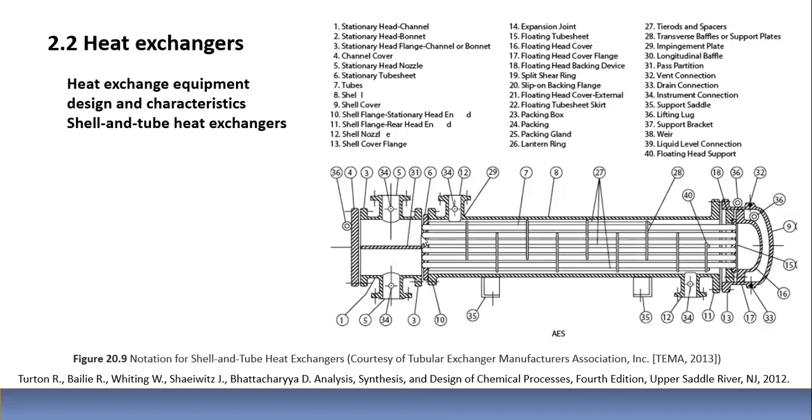En corte, se observa así. Usted ve los tubos soldados en el espejo. Mire que usted puede retirar este cabezal. Implica, según el dibujo, que eso está apernado. Pasa un perno, pasa una tuerca y seguramente en el círculo del cabezal, en el círculo de esta brida, esto es una brida, se ve el corte aquí, acá hay otra brida. A lo largo de ese círculo de la brida, usted puede ver esta línea aquí, por donde va a pasar el perno. Se aprieta con una tuerca y se hace un torqueo en cruz hasta que se aprieta todo. Del lado del cabezal, lo mismo se hace del lado del cabezal posterior.